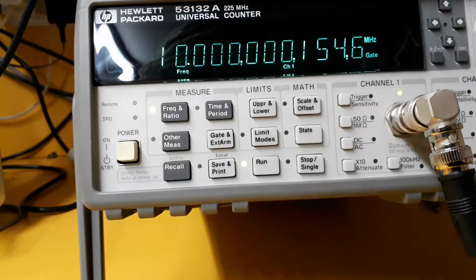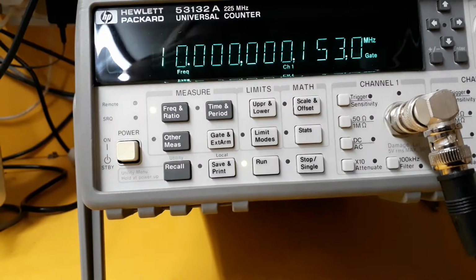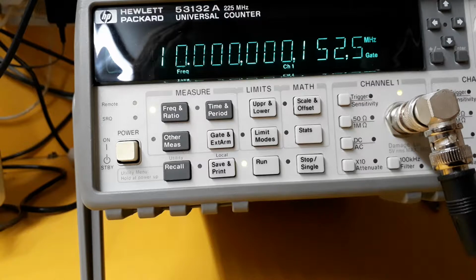And it's actually not too bad. It's been on a few hours now, so the oven's warmed up and it's nice and stable. And it's only 0.15 hertz out, according to the signal I'm getting from the GPS DO. It's just reading slightly high. Obviously the crystal oven is running a bit higher than 10 megahertz. So I thought I might just try and do the calibration on the crystal oven.